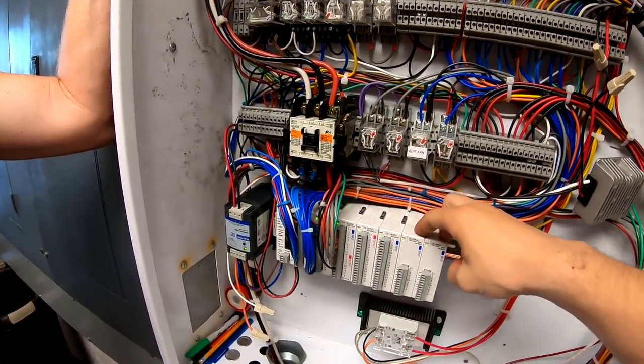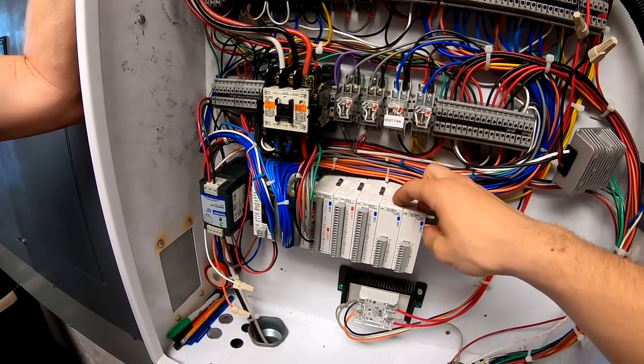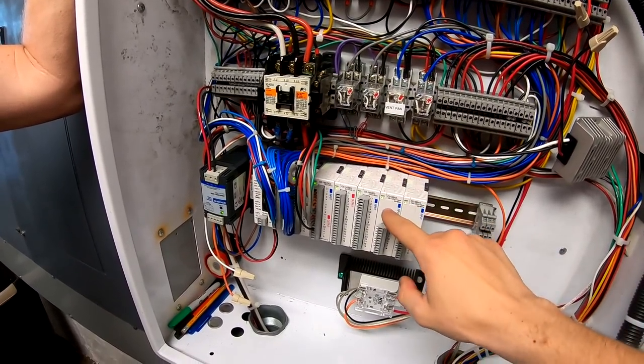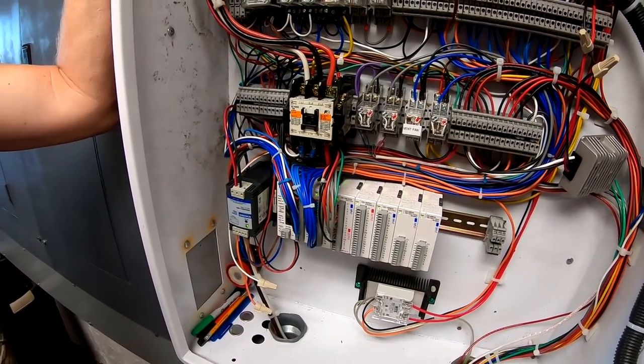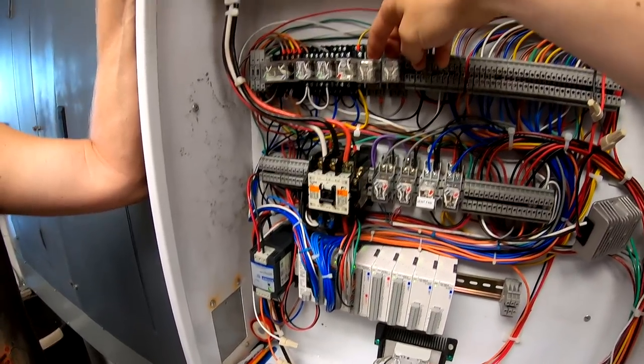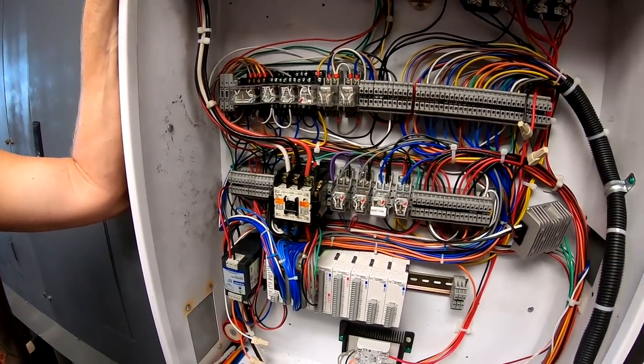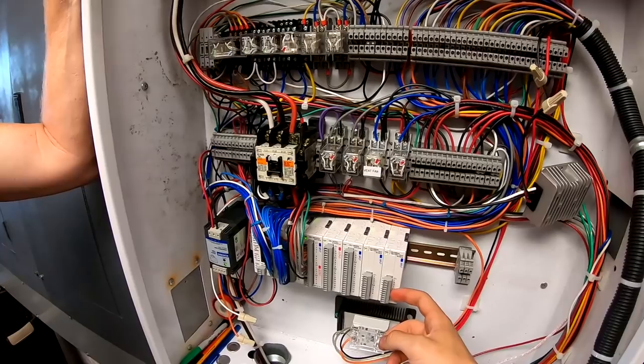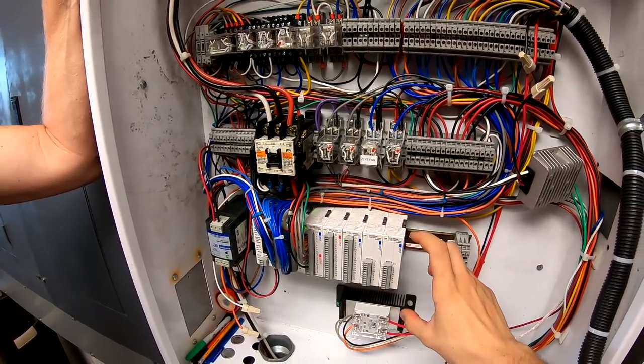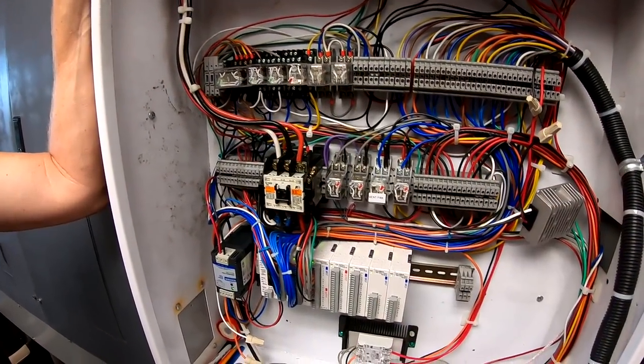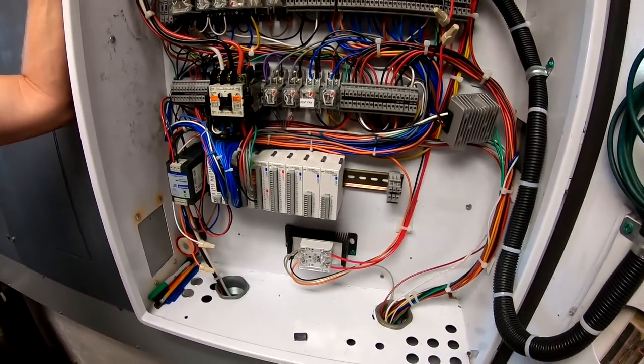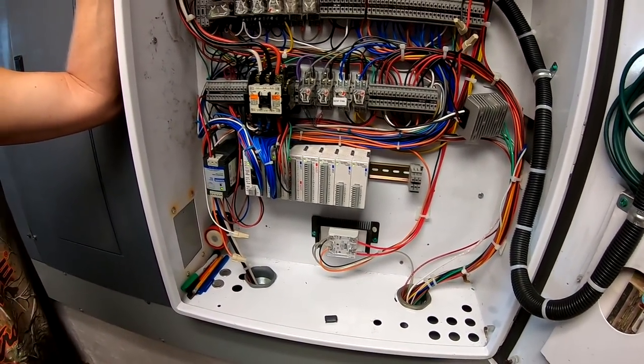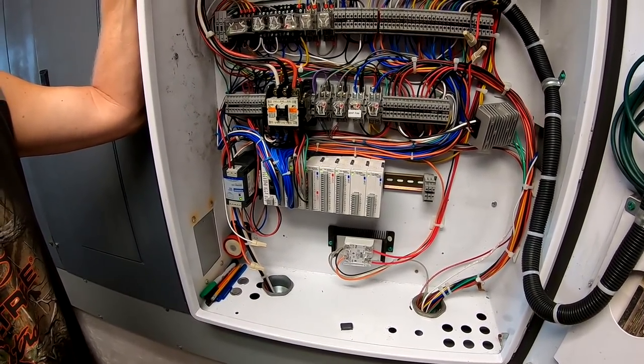So like these two right here are identical, but I just added those because those are 120-volt inputs. So instead of having these two relays right here that detect when the power is coming from the generator, it'll go straight into here and then the system can look at them a lot better than these two relays can. And if there's any sort of odd input signal, any fluctuation, something drops out...